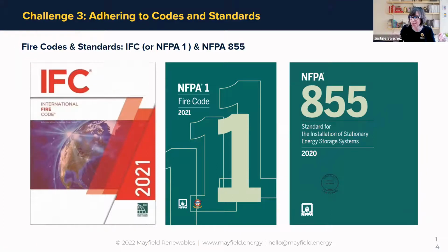Not only whether it's just IFC or NFPA 1, but what edition - are you in 2015, 2018, or 2021, which is going to be the most stringent rules when it comes to energy storage systems? These types of rules cover things like vehicle impact protection, fireproofing on your wall assembly - do you have a 1 hour or 2 hour fire rating on that assembly if you're going to put energy storage within a room - ventilation requirements, the maximum allowable quantity within the room, the maximum per unit, and the spacing required between units.